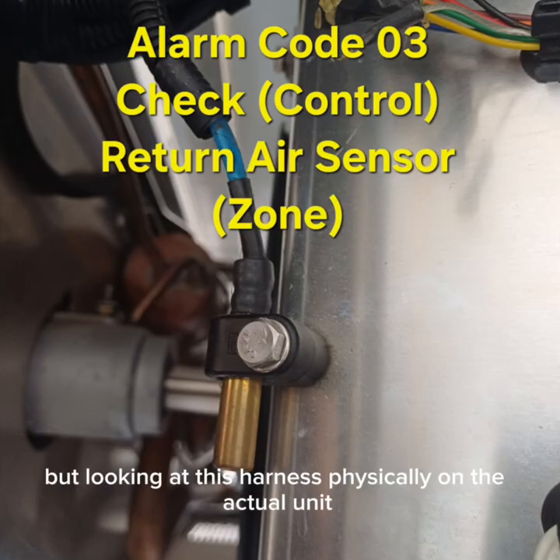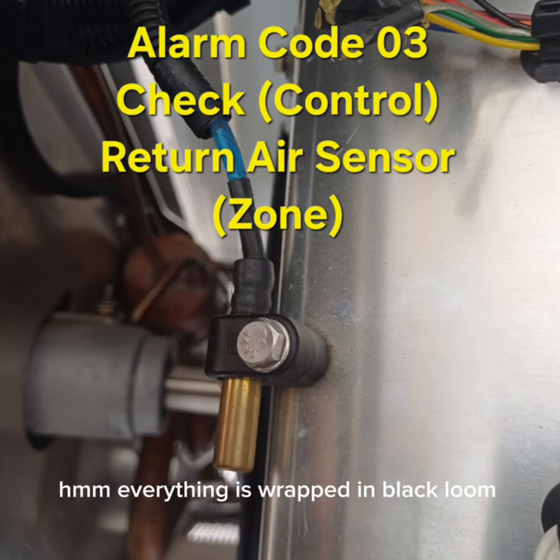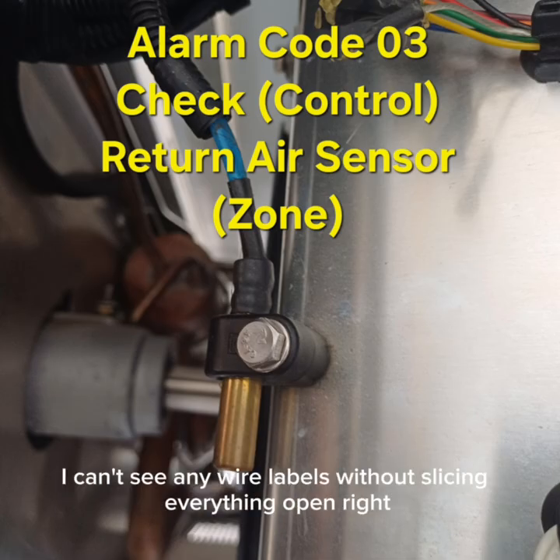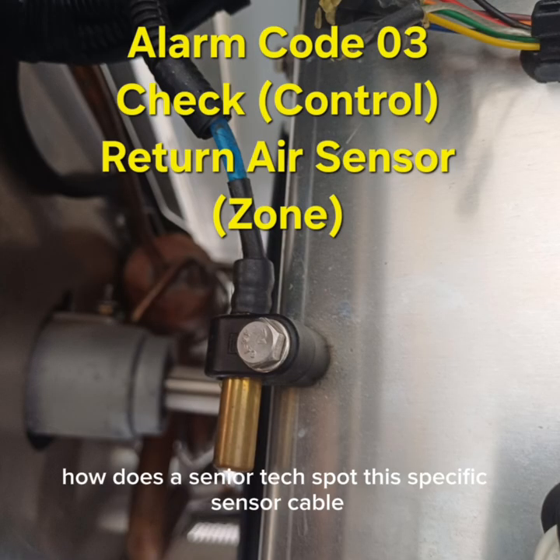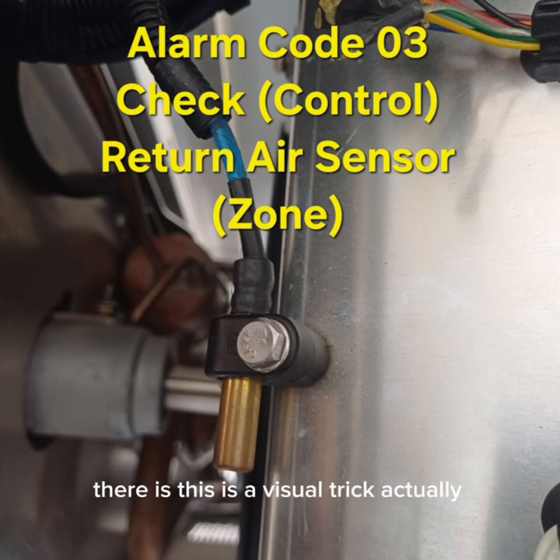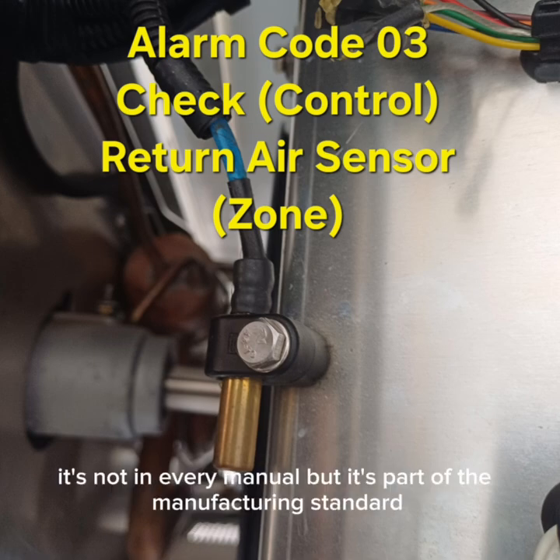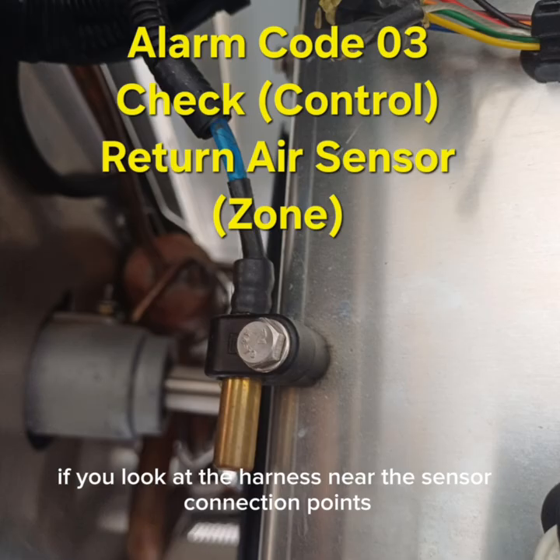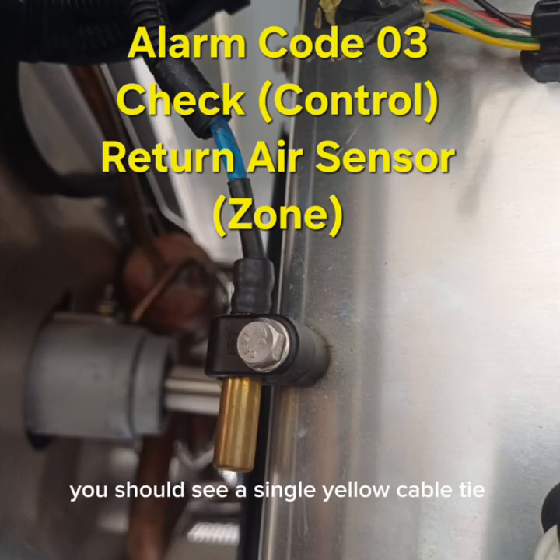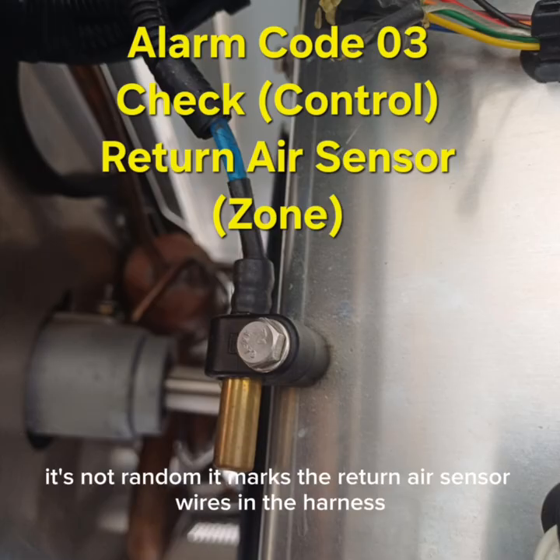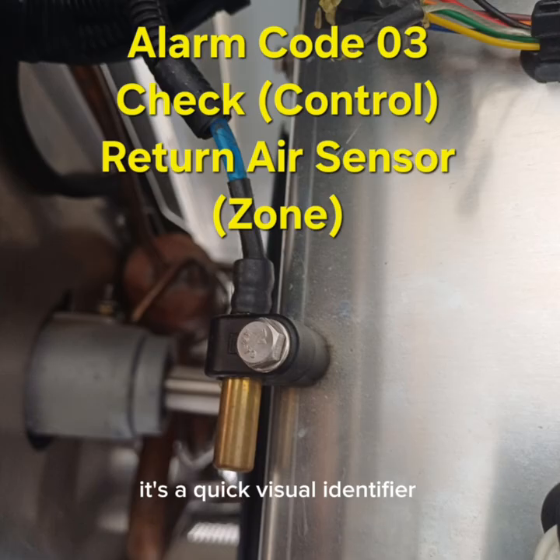But looking at this harness physically, on the actual unit, everything is wrapped in black loom. I can't see any wire labels without slicing everything open. Right. Is there a cheat code? How does a senior tech spot this specific sensor cable without stripping the whole harness? There is a visual trick, actually. It's not in every manual, but it's part of the manufacturing standard. If you look at the harness near the sensor connection points, you should see a single yellow cable tie. A single yellow zip tie, just a random one. It's not random. It marks the return air sensor wires in the harness. It's a quick visual identifier.